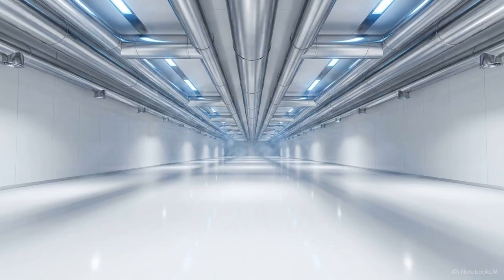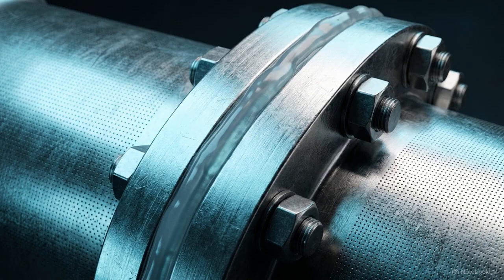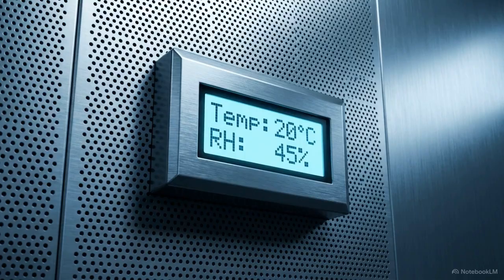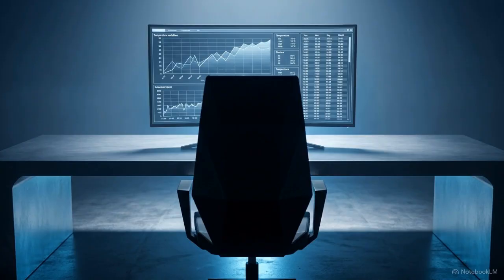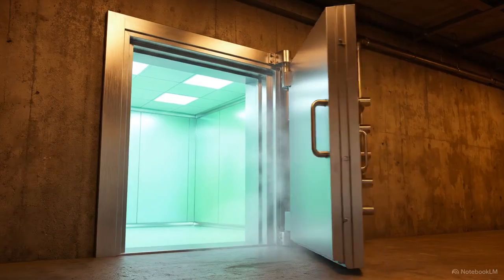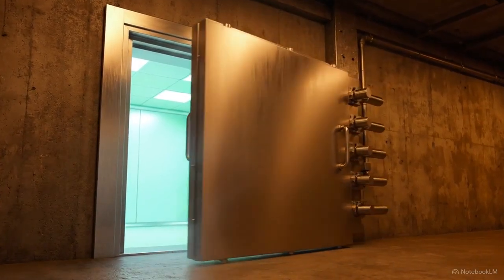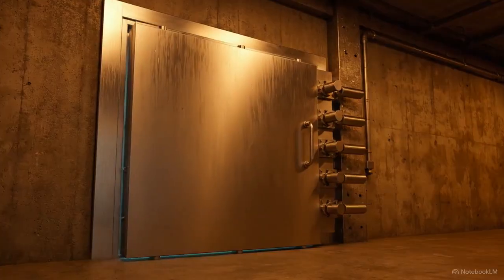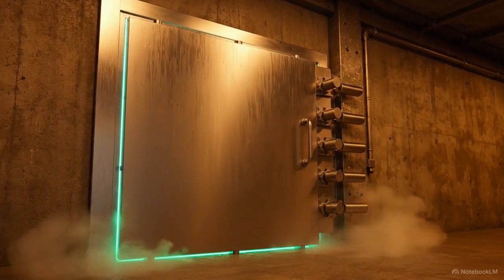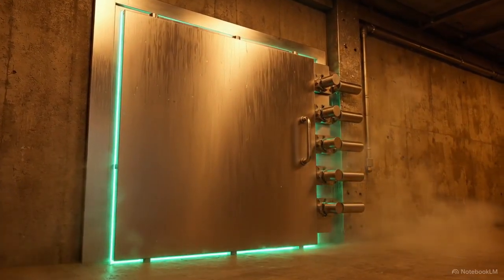Once purified, stainless steel ducts deliver this clean air uniformly across the rooms. Every joint in this ductwork must be perfectly sealed to prevent outside contamination from leaking in. Meanwhile, digital sensors continuously map the facility. They feed real-time temperature and humidity data back to the AHU, allowing for constant micro-adjustments. These physical components create a rigid, fail-safe architecture. They ensure the theoretical air cycle remains sterile in physical reality, day after day.